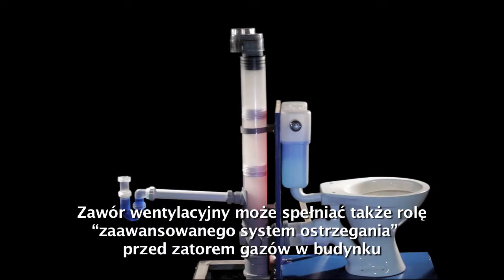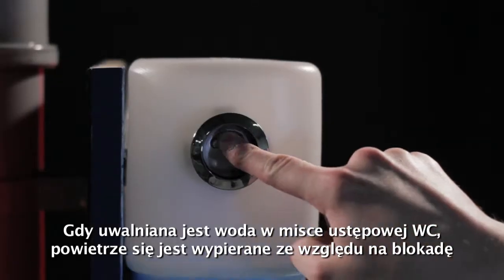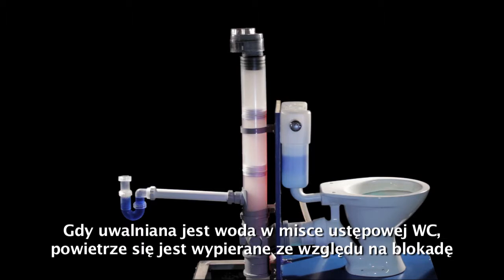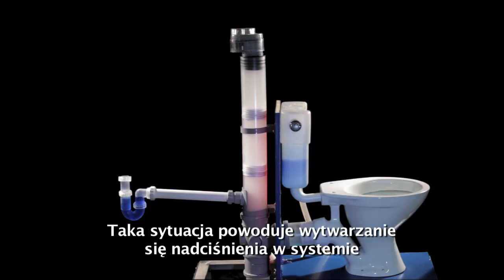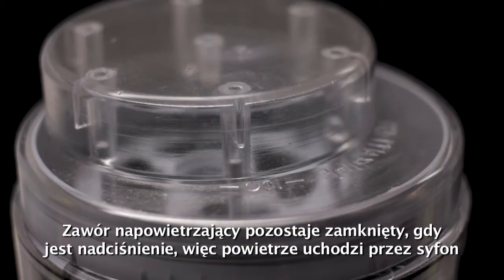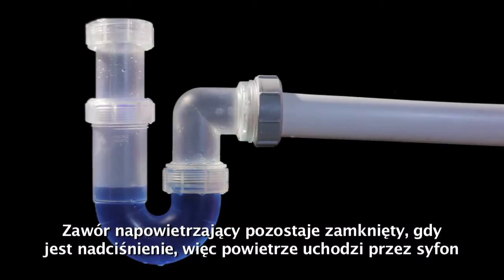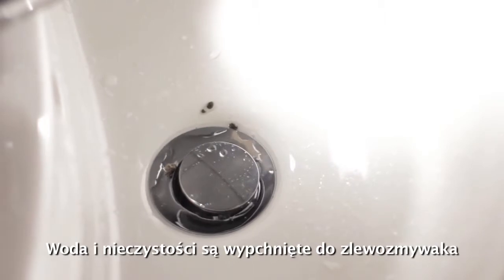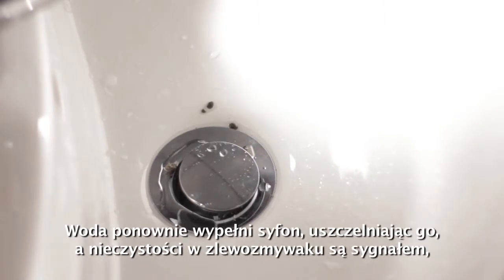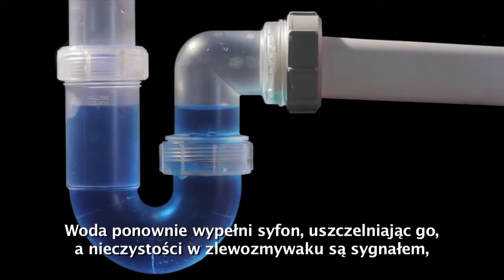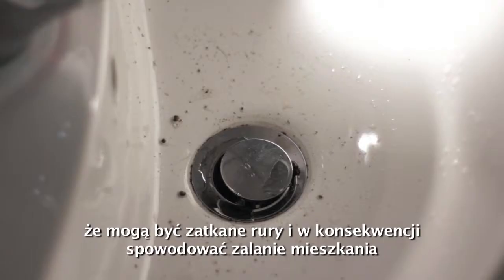An AAV can also act as an advanced warning system against blockages in the building sewer. When the WC is discharged, no air is displaced due to the blockage. This creates positive pressure within the system. The AAV remains closed during positive pressure, so air escapes through the trap. Water and debris are forced up into the sink basin. Water will drain back into the trap, sealing it, and debris left in the basin would highlight the blockage prior to any flooding.